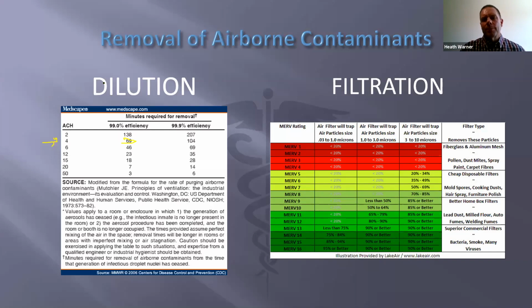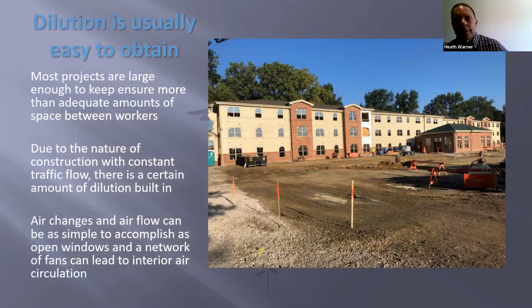The other side of the coin is filtration. When you talk about filtration, it surprises me the number of people that don't actually realize there are varying levels of filters available, everywhere from MERV 1, which is the red zone, clear all the way up to MERV 16. They actually go all the way up to 20. And then there's one above that. But for construction, filtration is going to be kind of an issue. So most of the time, until you can get a permanent system up and running, in construction anyway, we are stuck using dilution. Pros and cons to it.